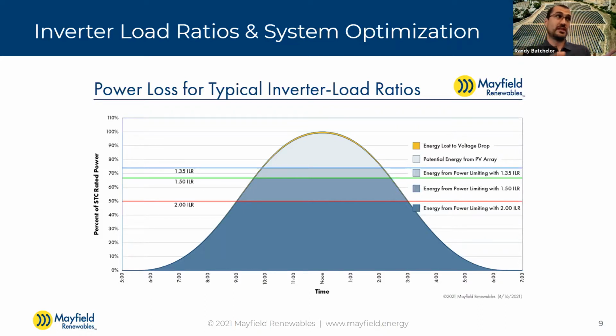Some hyperclipping happens in these high loading ratio, high VOC scenarios, and some is acceptable - you might get 12 hours a year or so. But in some scenarios it happens a lot and becomes majorly detrimental. You go from clipping of 5%, 6%, 7% up to 20%, and there's this major jump where your clipping goes out of whack. That's because of the hyperclipping scenario where you miss the voltage window entirely. So something for everybody to be aware of.